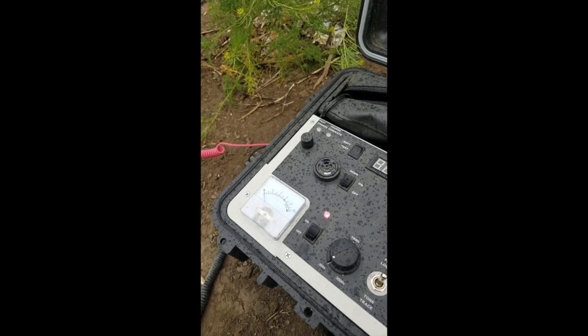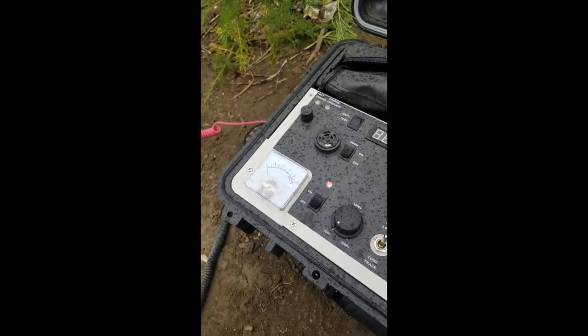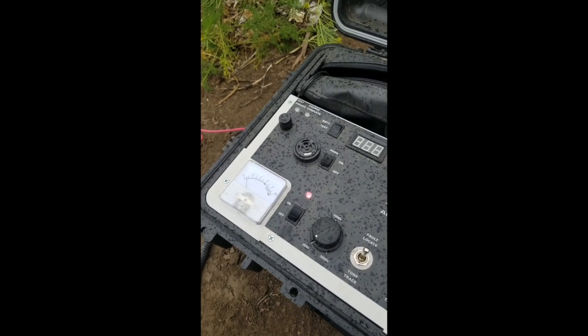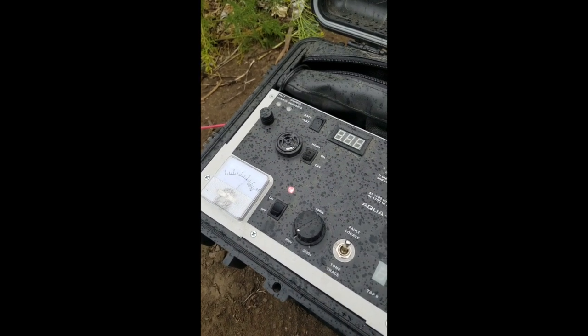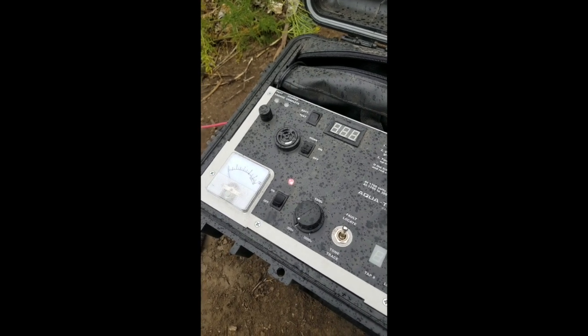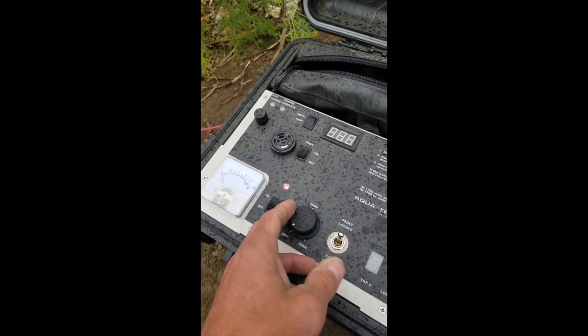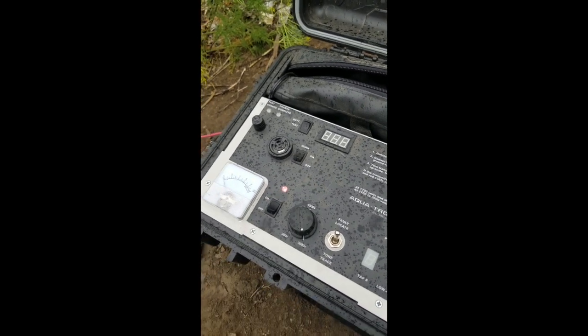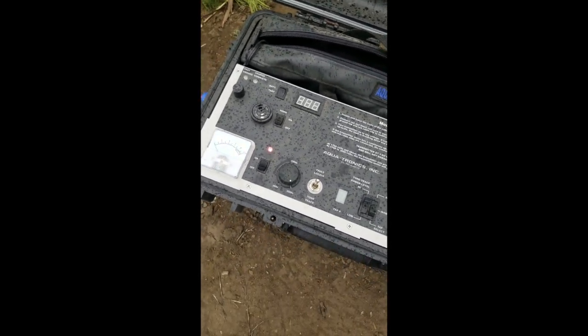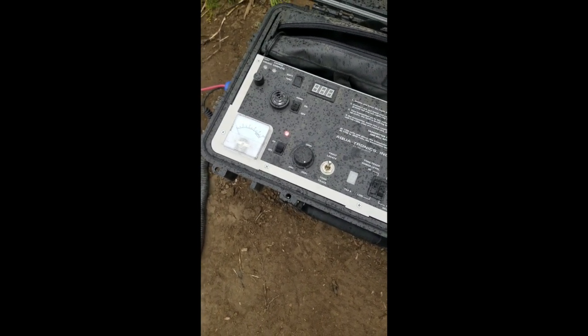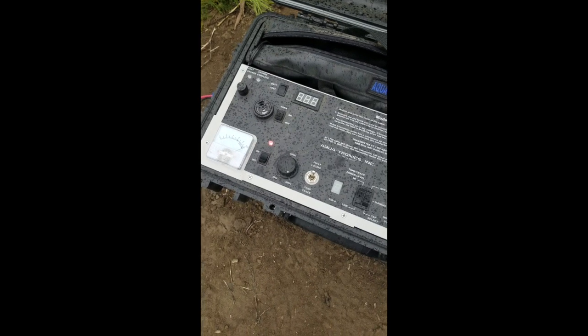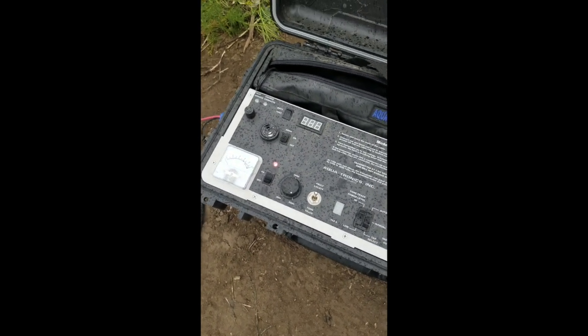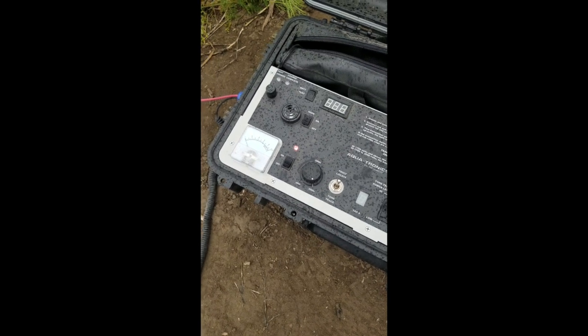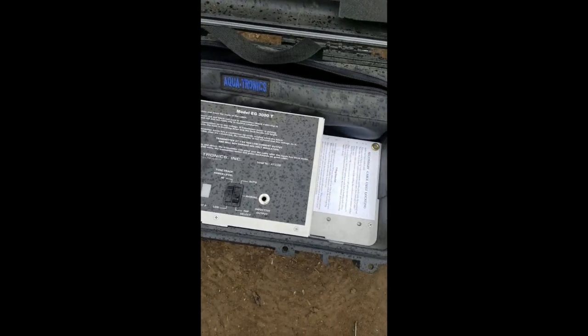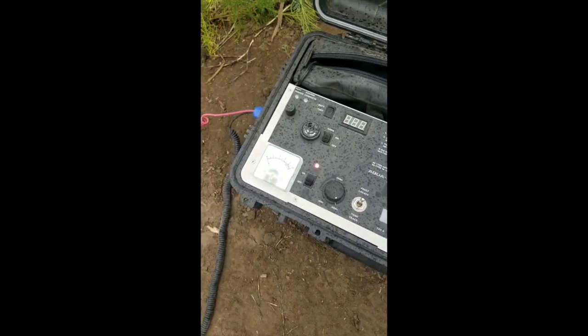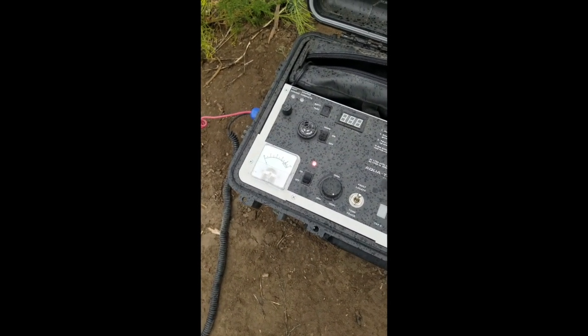So throw the instrument back on. 300 volts, we're showing we've got a good fault. And with any fault locating, before I go out to actually do the pinpoint, I generally just run the voltage all the way up to 3 kV. You're not going to damage your cable at 3 kV. We limit the output current in the device. But the instrument does have the potential to give you a full 3 kV pulse if the conditions at the fault change and it needs to have that extra voltage to keep the fault active. So I'm going to go ahead and set up my detector and get ready to go pinpoint this fault.